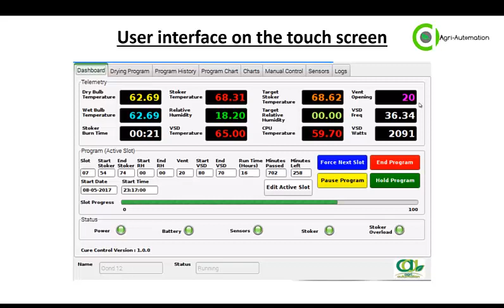So basically, you can create slots. A slot is a starting point of the temperature and an ending point, a starting relative humidity value and an ending point, or a static value of the vent. So either you've got targets here or a static vent. Like here you've got no targets but the static vent set. If you give it targets or the slope, the controller will do that, but if you give it a static value, it will ignore those. You can then give it the start and end of the VSD. We've now added a coal percentage here, where you give it the percentage of coal you want during that slot, and then the time. You can also save that program to a preset or load a preset.